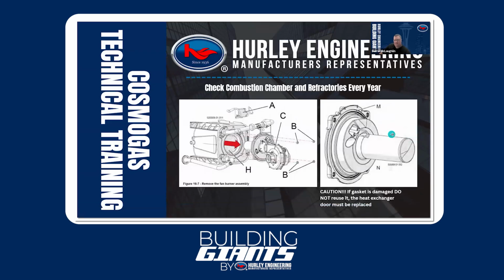Now looking on the inside, one of the most important things during service to keep track of are these front refractory plates here. Over time, if they've had condensate back up for some reason, or they've been dropped or pulled out abruptly, you will get cracks in this. And if it gets too big of a crack, that heat and temperature and flue gas will get through that crack and hit the aluminum backplate. And then that'll overheat and warp and it won't seal correctly.